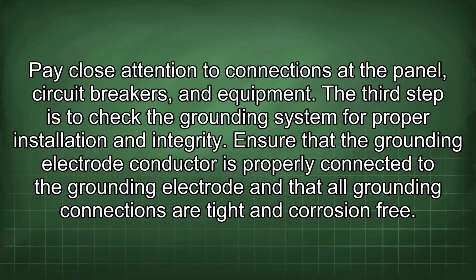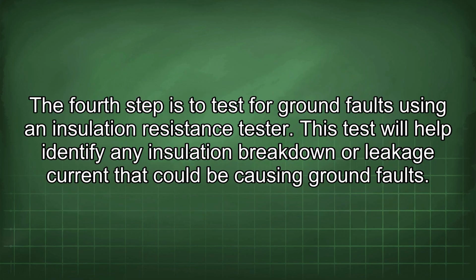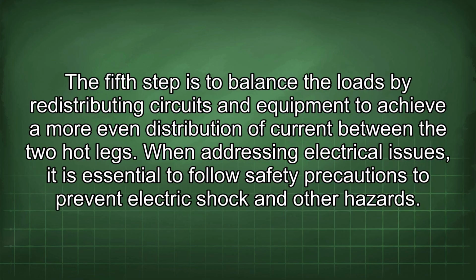The third step is to check the grounding system for proper installation and integrity. Ensure that the grounding electrode conductor is properly connected to the grounding electrode and that all grounding connections are tight and corrosion-free. The fourth step is to test for ground faults using an insulation resistance tester. This test will help identify any insulation breakdown or leakage current that could be causing ground faults. The fifth step is to balance the loads by redistributing circuits and equipment to achieve a more even distribution of current between the two hot legs.